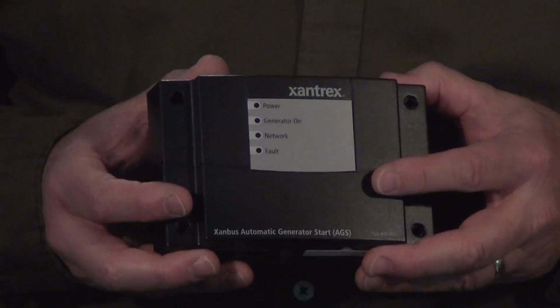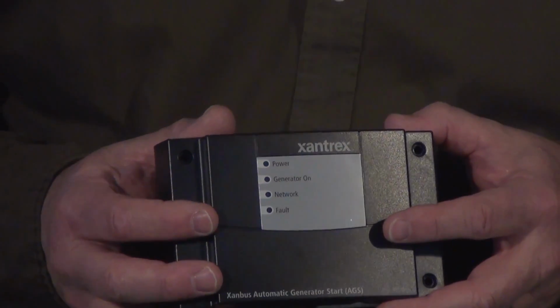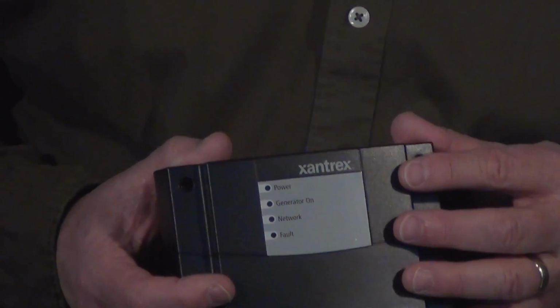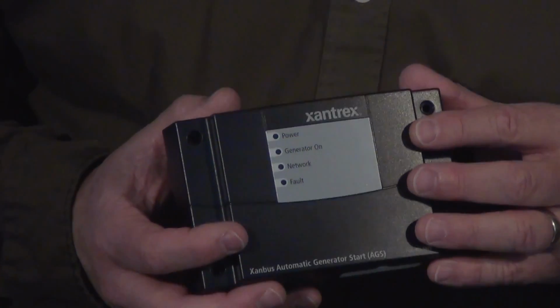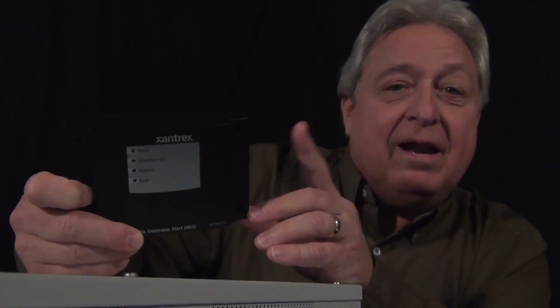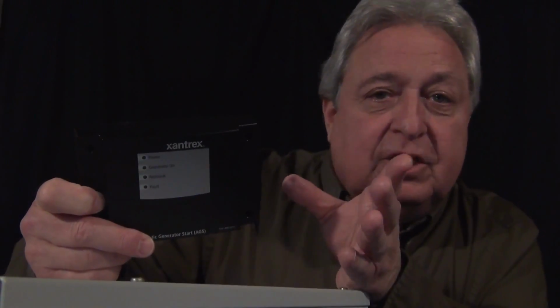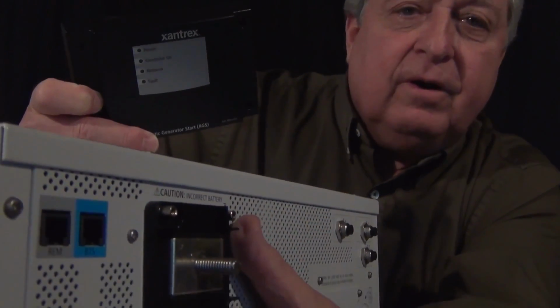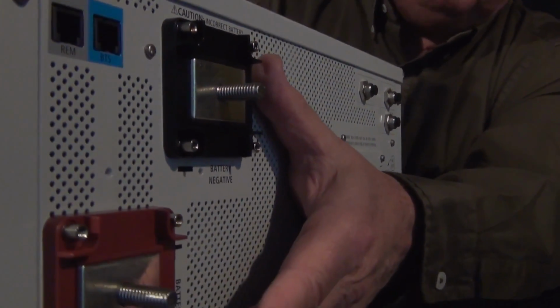Since I mentioned starting the generator, let's take a look at another piece to this amazing system, the Automatic Generator Start, or AGS. In my opinion, the coolest thing about the Xantrex AGS is that it continuously monitors the state of charge of the battery bank. And if the battery bank drops too low in voltage, the AGS kicks in, starts the generator, and that allows the inverter to bring that battery bank back up to full charge.